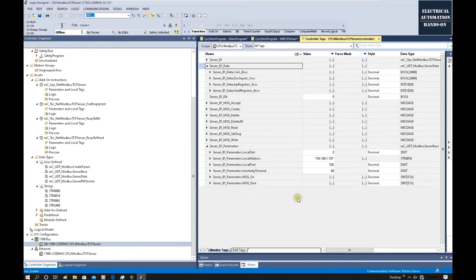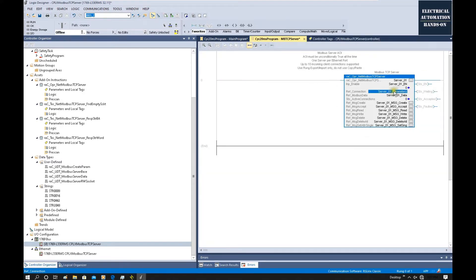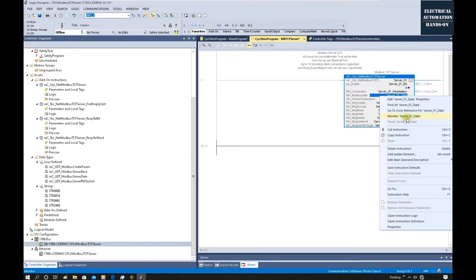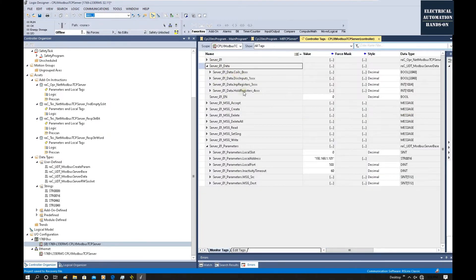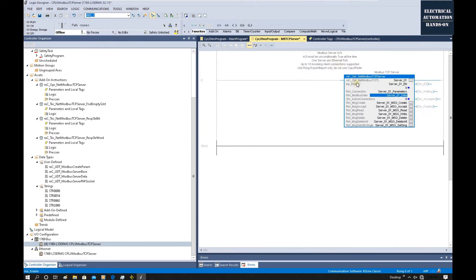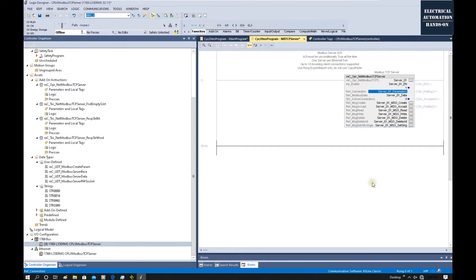You may ask where the actual data is located. That is in server_01_data. If we go back to the function block side, we just set the parameters and the Modbus data is located in server_01_data. Right-click and click Monitor. From here, we can see how the Modbus addresses are used. We will use function code 03 or 16 — basically within these two function codes, we use the 40,000 Modbus address area. Now, to enable this Modbus TCP server function, don't forget to change the enable bit to one. This will enable the server function.